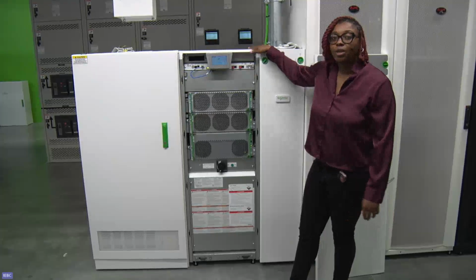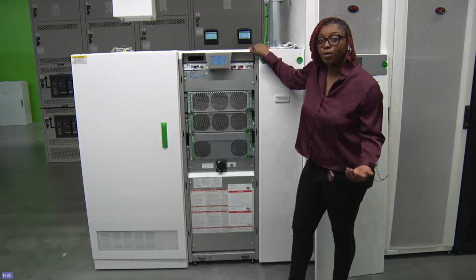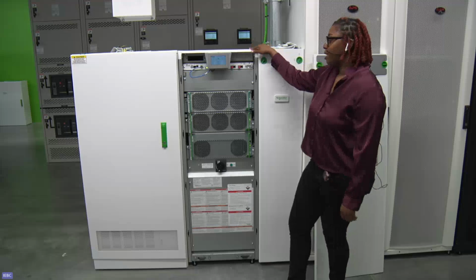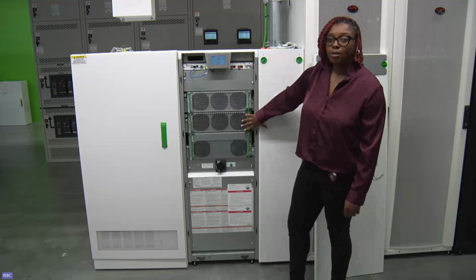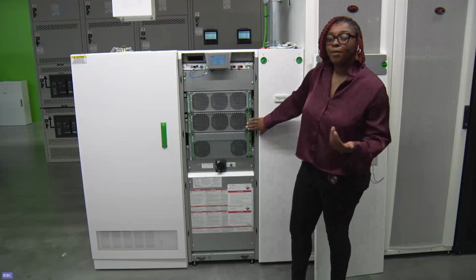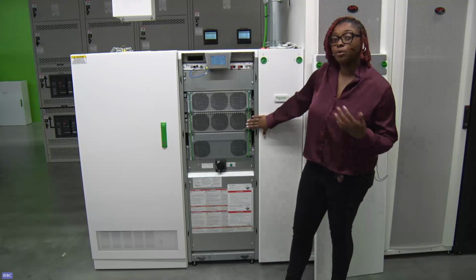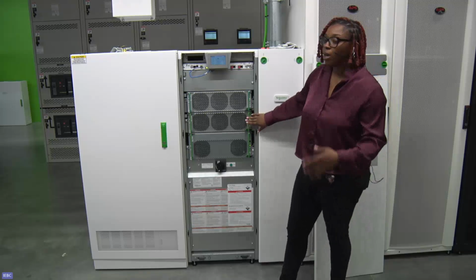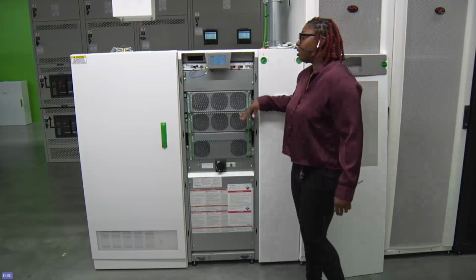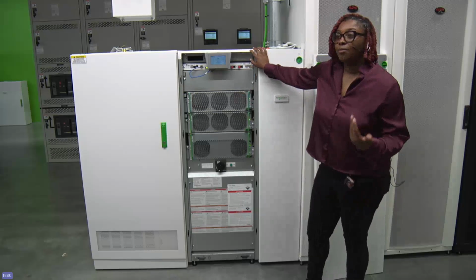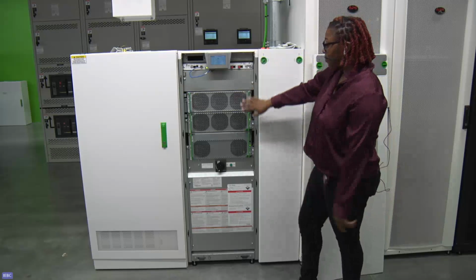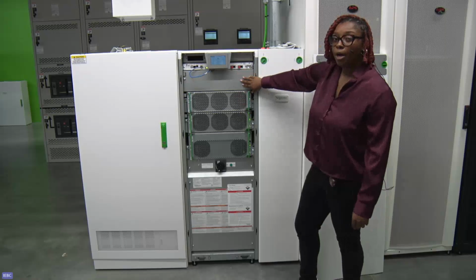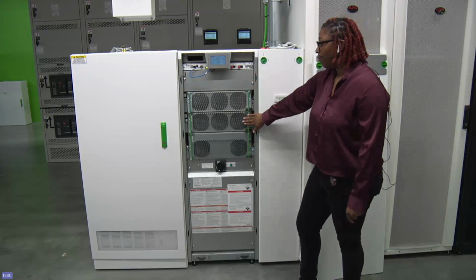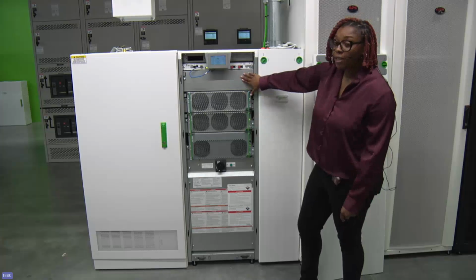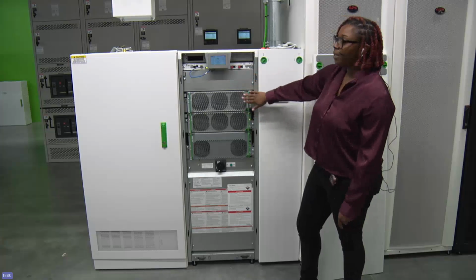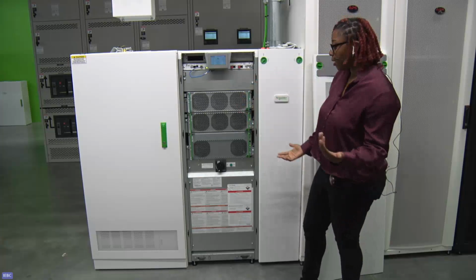With our Galaxy VS, they could output 480 volts or 208 volts. So when it comes to our power modules, if we're outputting 480 volts, it's a 50 kW power module. But if we're outputting 208 volts, split it in half, and it's a 25 kW power module. This is the largest of our Galaxy VS catalog. You can get up to 3 power modules in here, so it can either be 50 kW, 100 kW, 150 kW, or 25, 50, 75 kW, depending on what you're outputting.